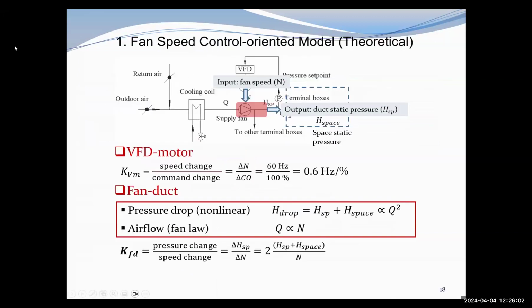So after the system setup, our second task is to develop the control-oriented model. This is a very critical step. To develop the control-oriented models, we have the theoretical approach and also the experimental approach. According to the theoretical approach, here we have this fan speed control system loop with the components of VFD motor and the fan duct. The VFD motor gain is the speed change over the command change. Normally, this is a fixed value.